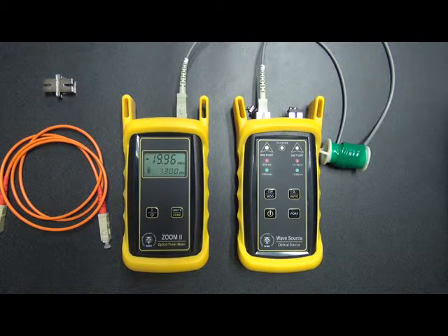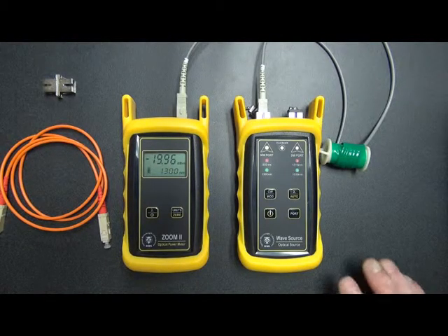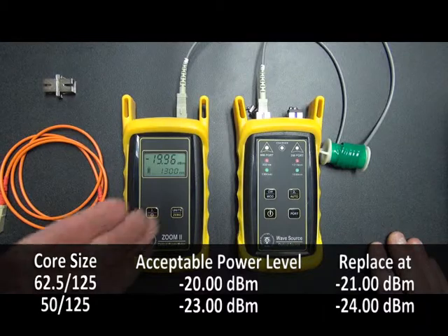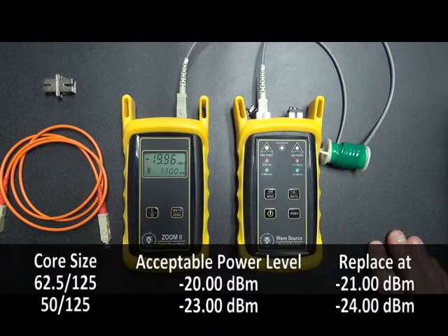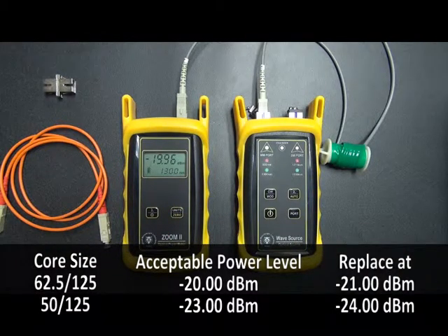Okay, notice we have a reading of minus 19.96 here. Again, very close to minus 20. In this case, it's a little bit higher, but we're not below minus 20. So we know that this patch cable is good, and we know that the units are within their NIST calibration.